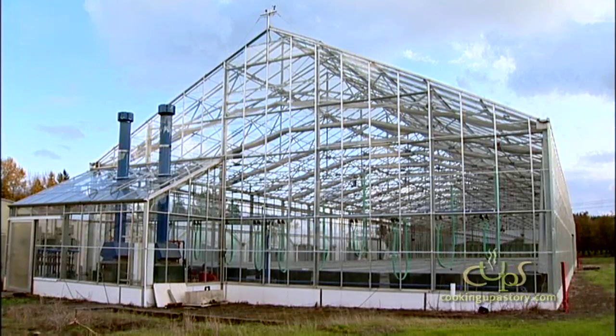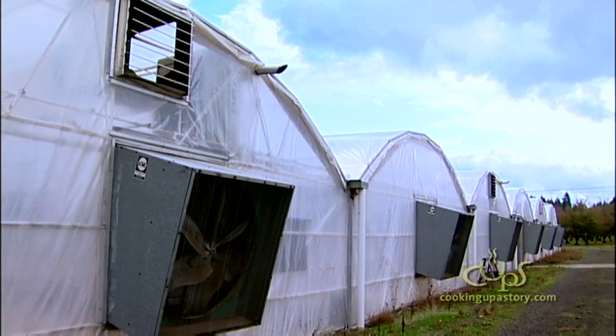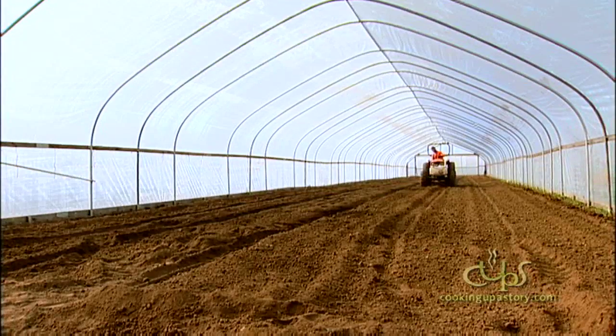For another farmer, looking at what we've experimented and learned from this greenhouse project, there are a lot of things, parts of it, that could be applied in a lot of different ways to other operations. If someone has an existing greenhouse that they're using LP gas or oil to heat, and they haven't built permanent structures or poured a cement floor, they could very easily trench that and do a vent collection tube in the peak of that greenhouse and try to conserve that heat that they're venting right now into the floor and have a warm floor that would radiate heat and keep that greenhouse warm during the day.